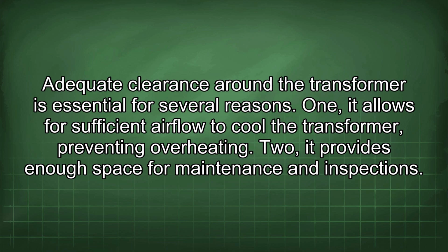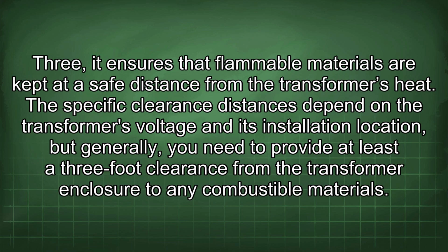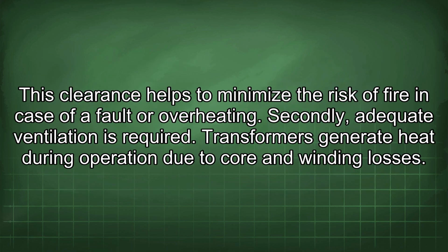1. It allows for sufficient airflow to cool the transformer, preventing overheating. 2. It provides enough space for maintenance and inspections. 3. It ensures that flammable materials are kept at a safe distance from the transformer's heat. The specific clearance distances depend on the transformer's voltage and its installation location, but generally, you need to provide at least a 3-foot clearance from the transformer enclosure to any combustible materials. This clearance helps to minimize the risk of fire in case of a fault or overheating.